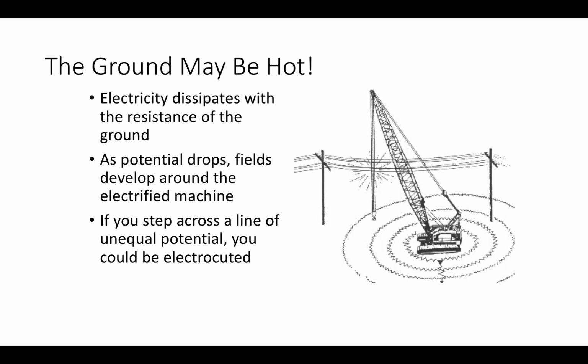So if you take a look at the crane picture on the right that's touching the line, there are different fields based on the resistance of the ground: wet ground, dry ground, different soil types. As you cross these field boundaries, you could actually have a difference in potential from one leg to another. Even though you think you're safe because you're walking on ground, you can actually be stepping across and providing a path of current from one field to another.